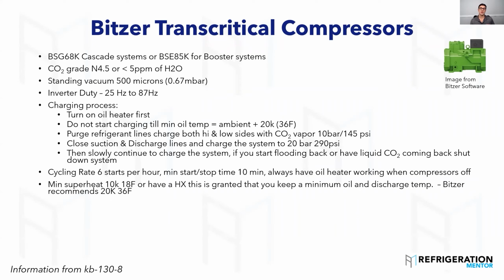Minimum superheat on this transcritical compressor is 10K or 18F. They want that because of the solubility that I talked about before. If you start getting below that, the CO2 is enriched, it's going to be enriched oil, and it's going to dilute the oil and cause bearing wear. A lot of them that I see are going to have a special design. They could have a heat exchanger, so what happens is it takes discharge gas into the suction and meters that in by an electronic valve to make sure you always stay above that. You'll see this definitely on the low temp side.